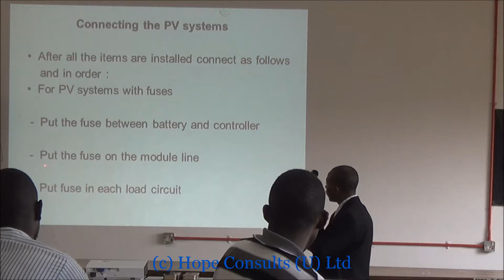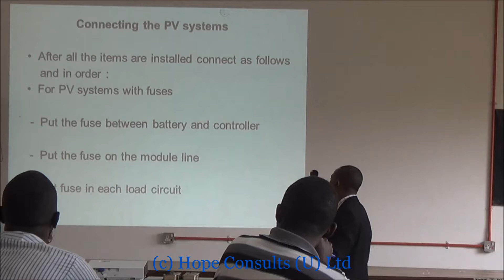You also put a fuse on the module line, between your module and the controller. You put a fuse in each load circuit, in line with the amount of energy the load is going to use, the current. That way, if any current comes that is greater than the current the load is supposed to use, you only lose a fuse, which is easier to replace than losing your radio or your lamp.